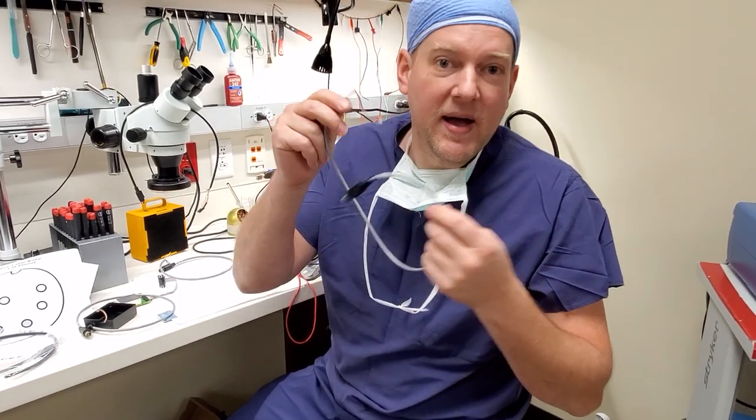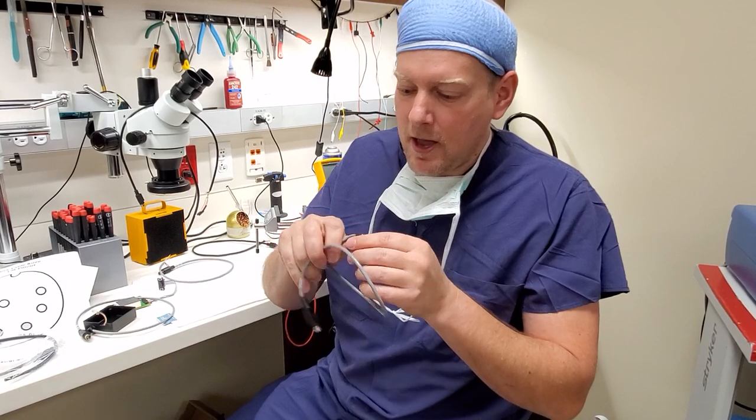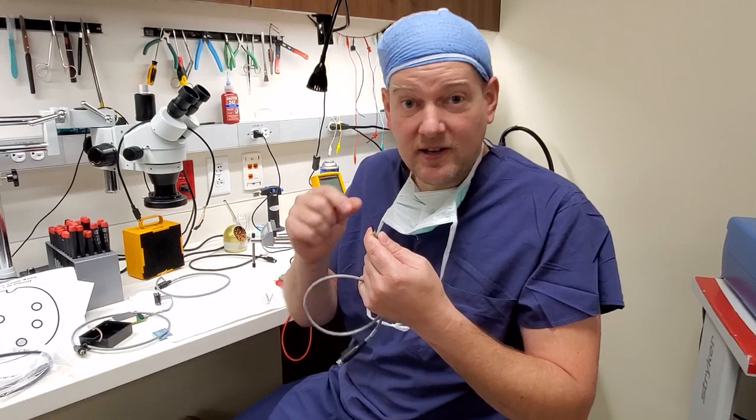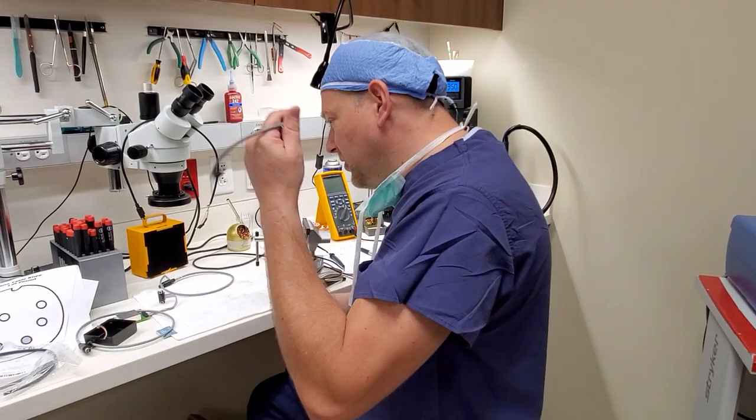Now you have to be careful because sometimes these terminated cables will be shorted pins. And that will tell the equipment what type of box is connected or vice versa. So the first thing I had to do when I did the pinout on this particular device is I had to pull the heat shrink off and verify that all those wires are just cut flush. They are not actually terminated, soldered together.